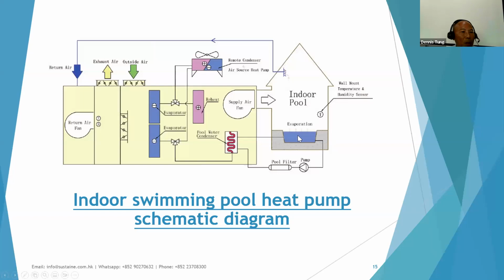So this is an indoor pool. The indoor environment is very humid due to the evaporation of pool water into the indoor pool hall air. Evaporation will absorb heat from the water, which becomes vapor and rises into the air inside the swimming pool hall. And this humidity must be removed by an air conditioning method, to keep the humidity down to a suitable level.